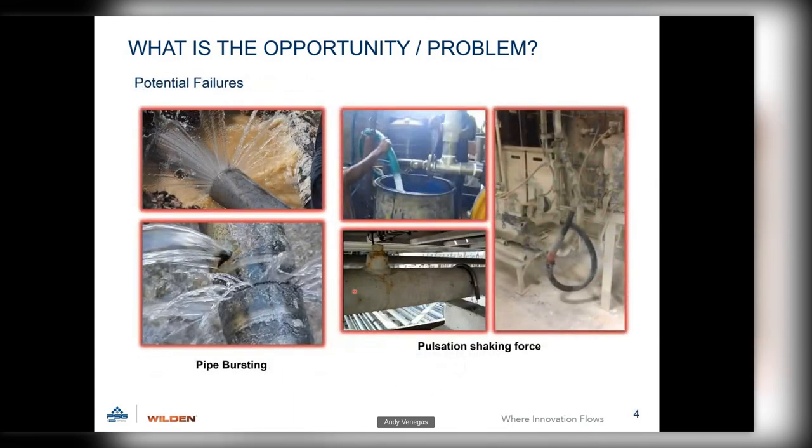Another common problem is customers calling because their piping has failed or burst. With pulsation in the plumbing, it attacks joints and welds, ultimately causing leaking, pipe bursting, or ruptures. With flexible hoses, they have to be chained, secured, or held by someone, because it's not like a garden hose — it's more like a whipping action. That whipping action puts a bending moment on the nozzle at the pump discharge, or causes the pump to flail around wildly.